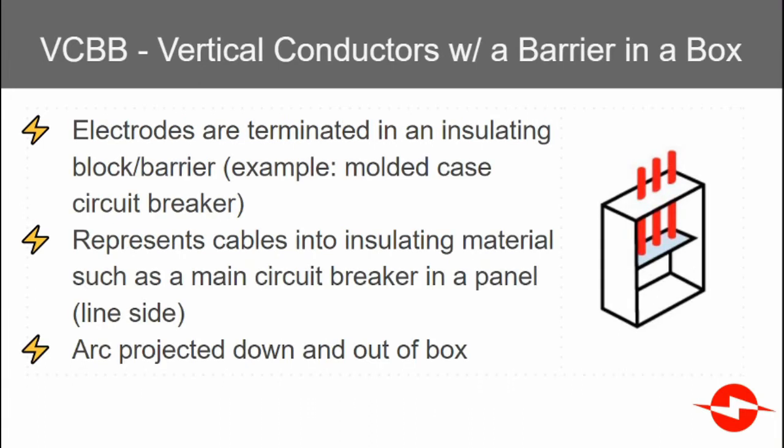The next configuration is vertical conductors with a barrier in a box. Electrodes are terminated in an insulating block or barrier — for example, a molded case circuit breaker. The arc is again projected down and out of the box, with relatively more incident energy compared with the previous configuration, due to the block or barrier reflecting more energy out of the box.